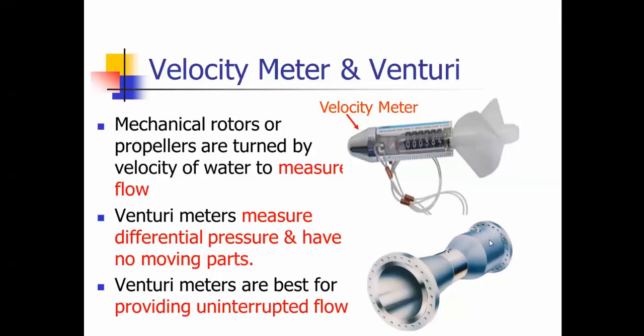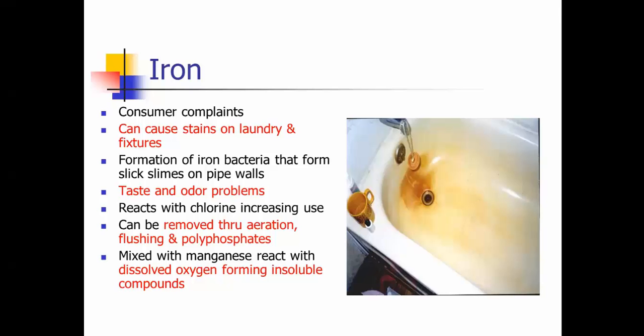Venturi meters, they use differential pressure between, there's a high and a low connection here, and you have a transducer that measures the differential pressure across those. There's no moving parts in them, and they're best for providing uninterrupted flow.